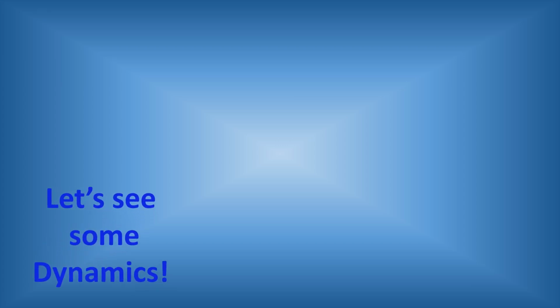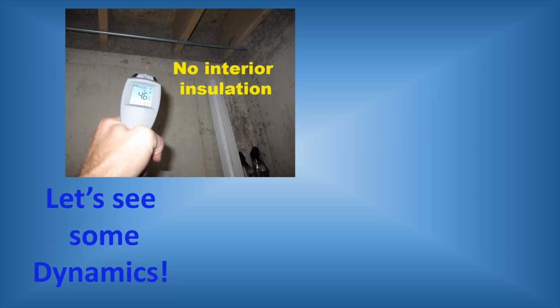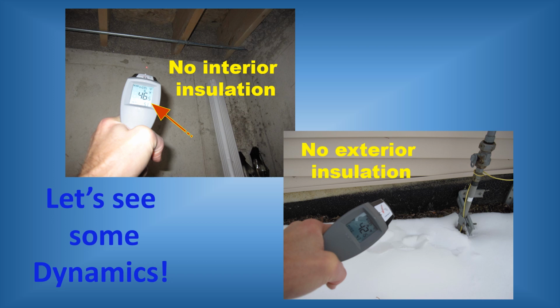So let's see some dynamics. Hey, Kev, it's in your company name. All right, what are we looking at here? This is the foundation in the basement, of course, with no interior insulation. And look at the number on the temperature heat gun, 46. Ooh, what's this? No exterior insulation, and it's 42. Now think about that. 46, 42, you mean there's only a 4-degree difference, and it's 30 degrees outside? You know what? There's a lot of heat loss going on there.